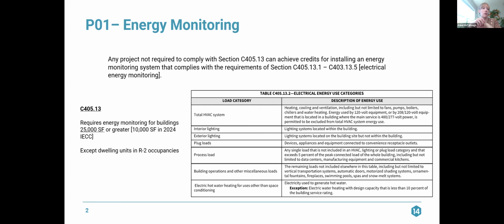But if you have electric water heating that is just generating domestic hot water, you would have to monitor that unless it is less than 10% of the building service rating.